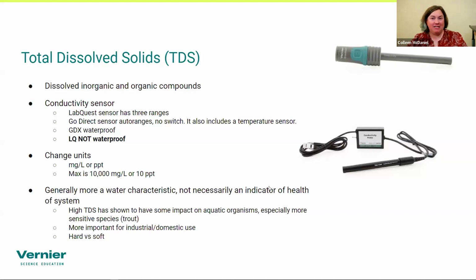The thing to keep in mind with total dissolved solids is because those are essentially looking at ionic concentrations, there are going to be some limits. So the max total dissolved solid reading we can get is 10,000 milligrams per liter, or that's equivalent to about 10 parts per thousand. That's where you're going to be above that freshwater level, but not full ocean water level. So I basically recommend, if you're going to be measuring things that are above 10 ppt, you're going to want to get a salinity sensor. Below 10 ppt, conductivity is going to work great, but you also might want to consider doing a dilution. So if you don't have a salinity sensor, you can use the conductivity sensor. You would just want to dilute your sample so that it's within the range of the sensor itself.